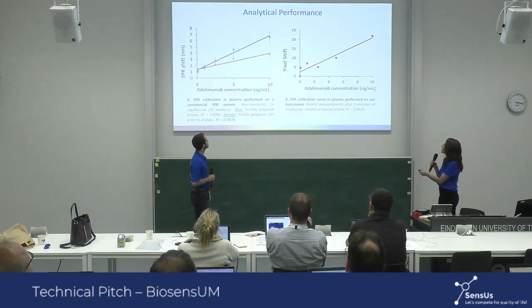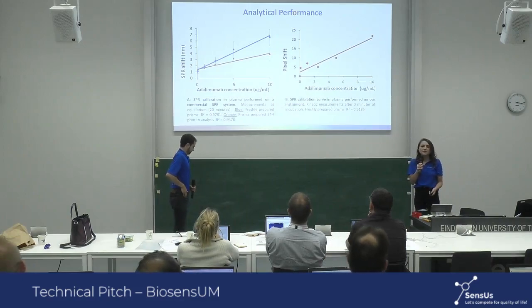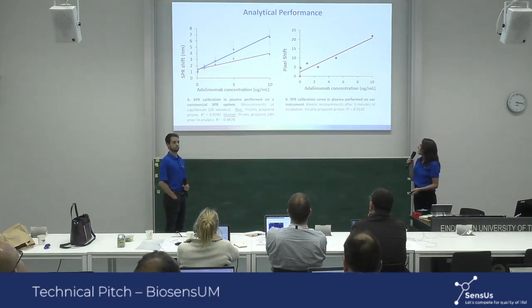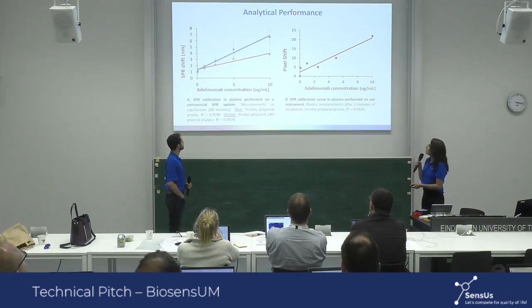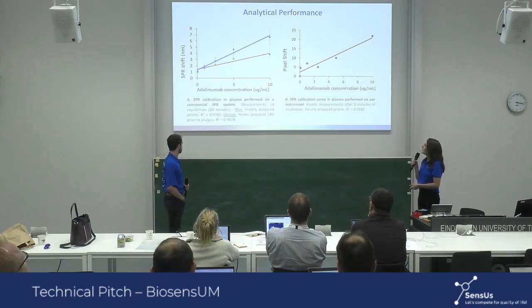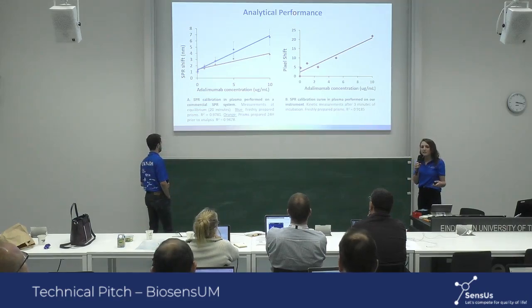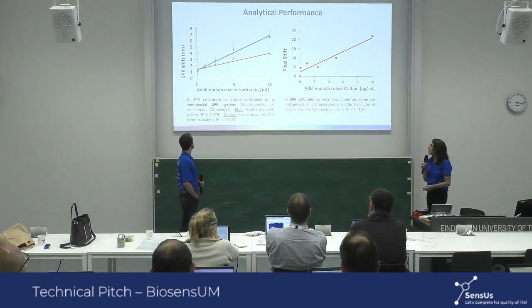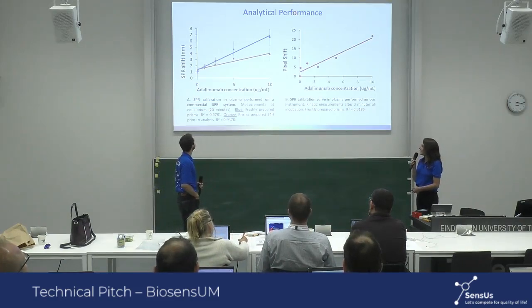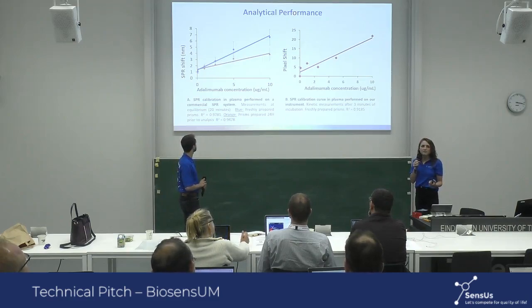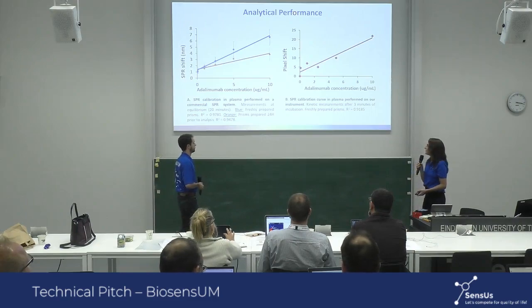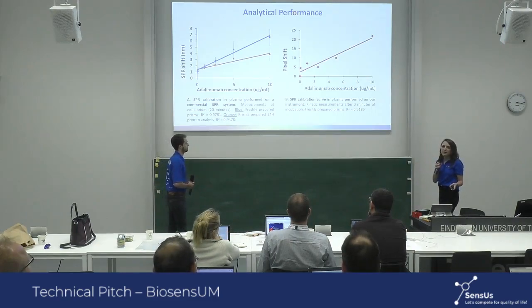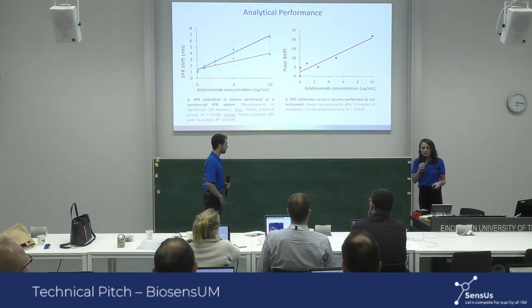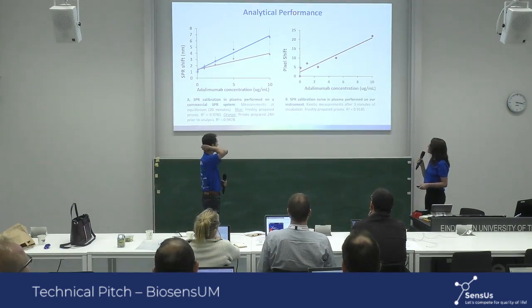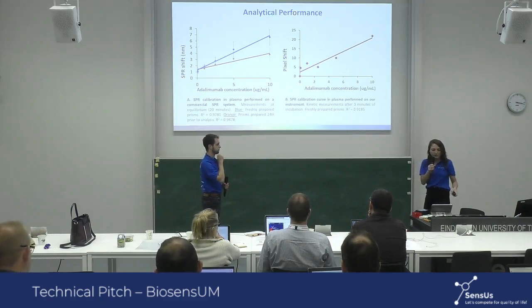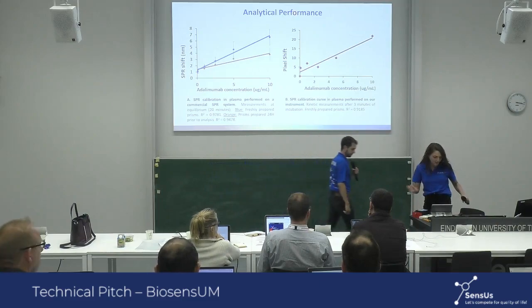We first validated our bioassay using a commercial SPR system and achieved good linearity, as you can see in blue in the first panel. And then we wanted to see if we could store functionalized chips for 24 hours prior to analysis. And we achieved, again, quite good linearity, which is a very promising result towards commercializing our sensor. And finally, we could transpose the bioassay using our own technology and got an R squared of 0.92, which was very encouraging. So now Jean-Antoine will talk to you.